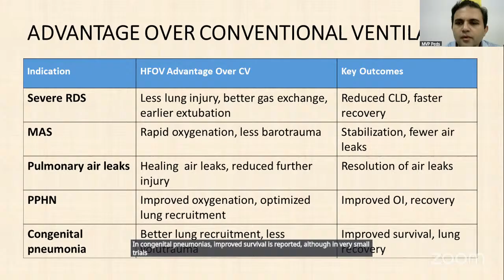Anytime you have advanced modalities like this, you must have basic protocols in your institute. So the initial settings are what we end up training residents very often is, we have to set a MAP that is 2 to 3 above what we already have on a conventional ventilator. We set delta P or amplitude to get just enough wiggle up to the umbilicus. The frequency is set at 10 to 12, I:E ratio at 1:1 or 1:2.